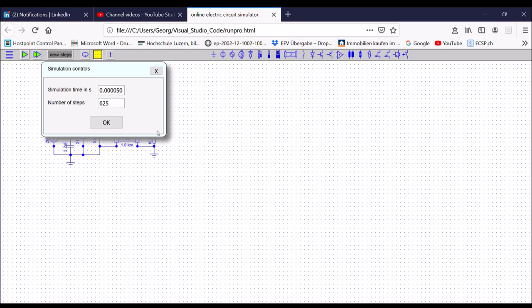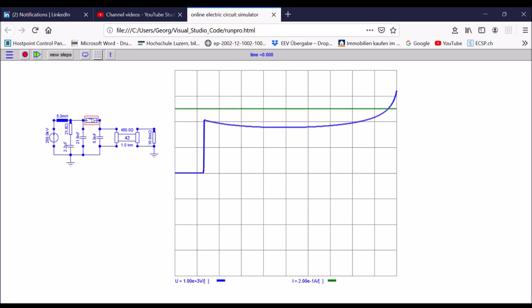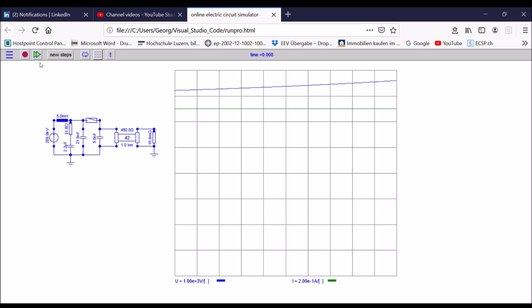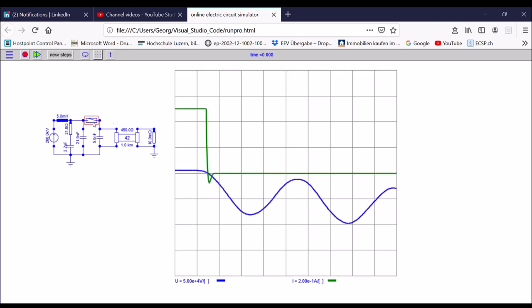First, let's go close to the current zero in 100,000 steps. So you see, first of all, two traces. One is this limited current trace, the green one, and the blue one is the arc trace for the arc voltage. And let's continue now our approach towards current zero. I have to approach it in steps. So here you see it clearly. This was now a successful terminal current interruption. You see here the current, the green one, and this post-arc current, this little tweak here. So the breaker was successfully interrupting this short line fault current.